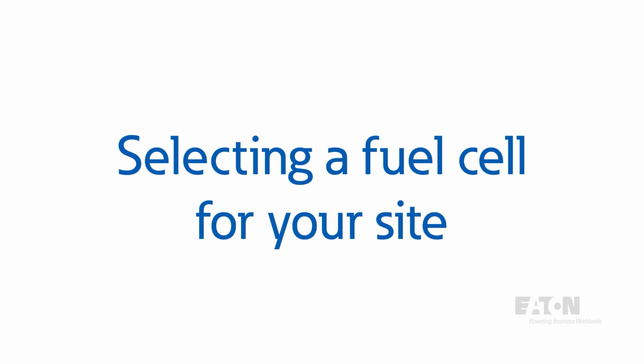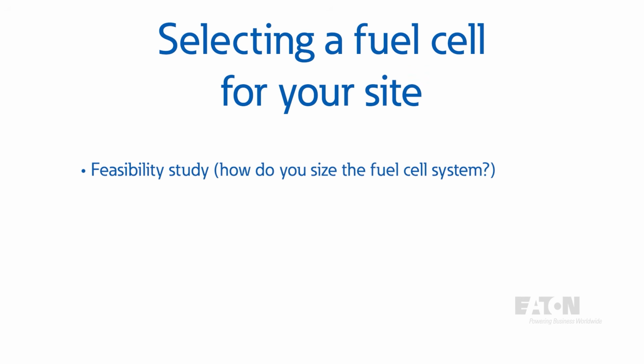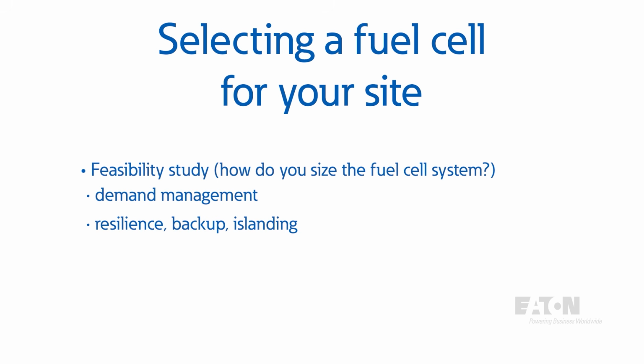So if you wanted to install a fuel cell at your site, what would you want to think about? Here are a few initial considerations. Start with sizing. A feasibility study will help you determine if a standalone fuel cell or one integrated with other DERs into a microgrid is appropriate. This will help you determine the cost-benefit of the installation. For example, if you can offset peak demands during the day when electricity is expensive, you can size based on this parameter. If you're looking for resilience and backup power with islanding capabilities, consider which loads are most critical and size based on that. Other considerations may lead you to size the system based on site-specific goals.